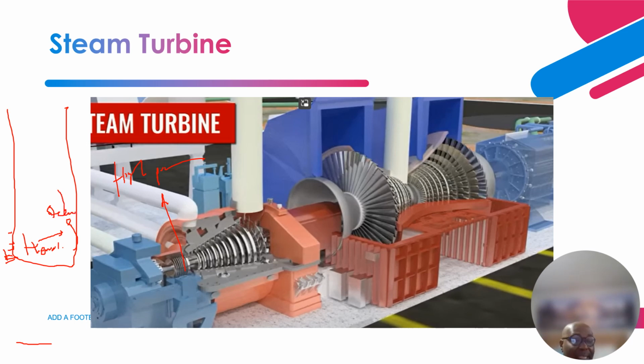And the steam basically rises up. Remember, the steam is about 70% dry and 30% wet. So the 30% stays here to wait for additional heating to evolve into steam. Since the drier part of the steam is lighter, it rises up into the reheater pendant. So it goes in here, and this reheater pendant is in the middle section of the boiler. That reheater section utilizes additional heating from the flue gas that is being emitted into the atmosphere. The flue gas has sulfur dioxide, carbon dioxide, and has latent heat embedded in it.